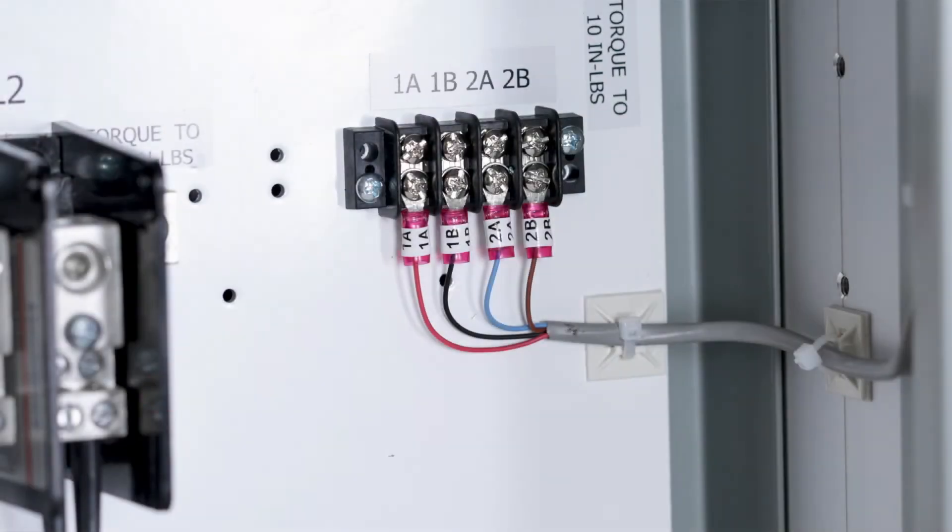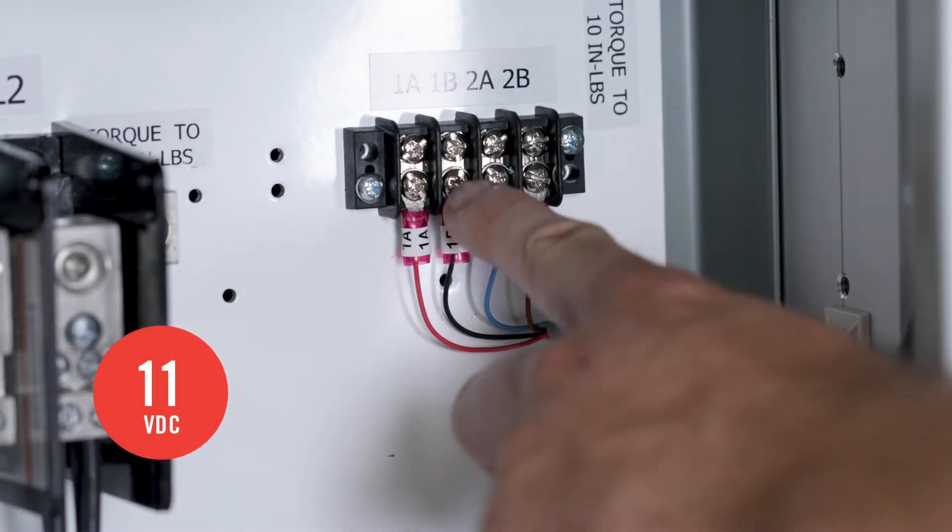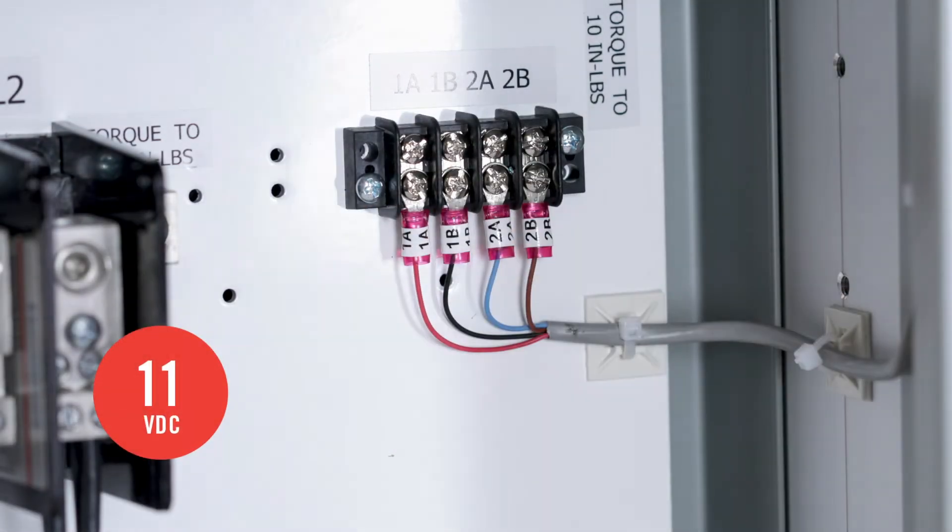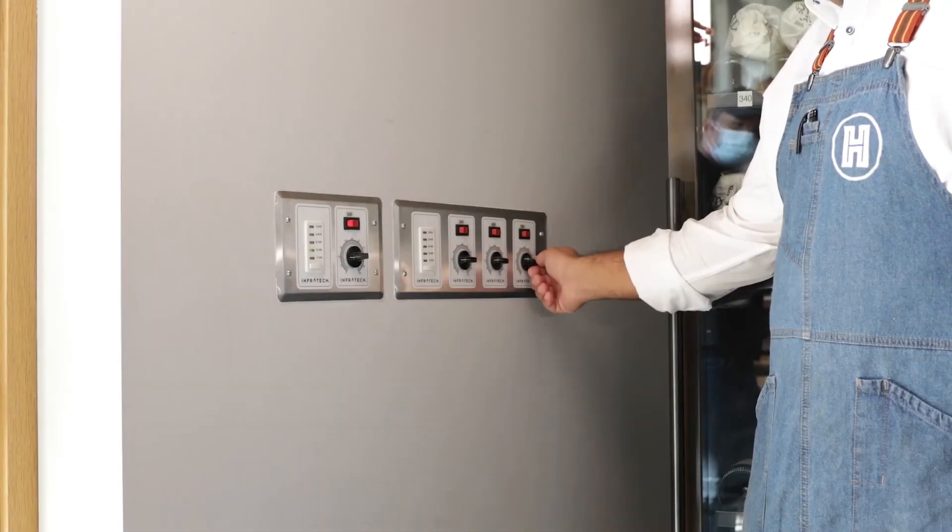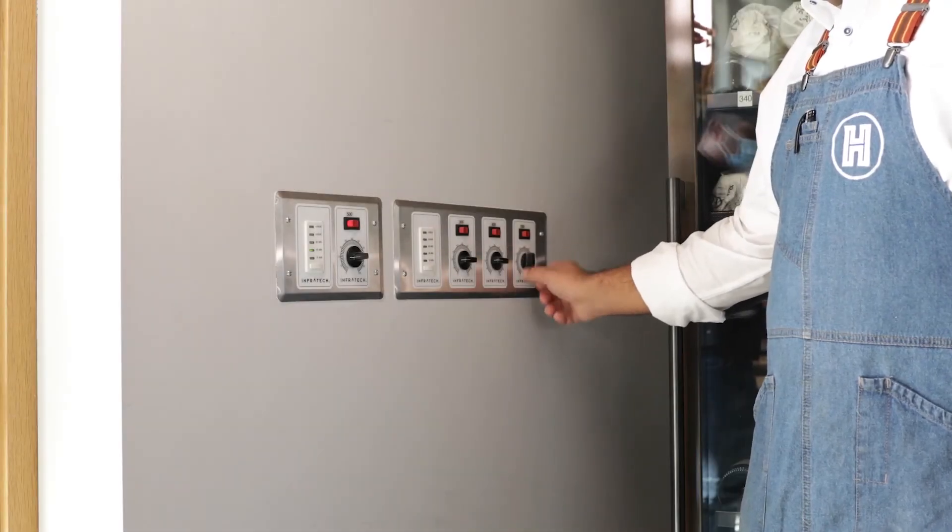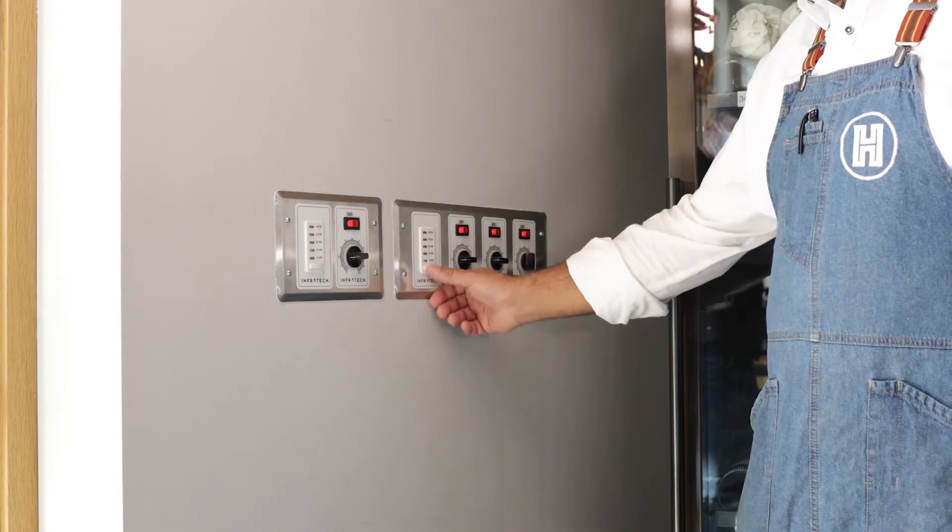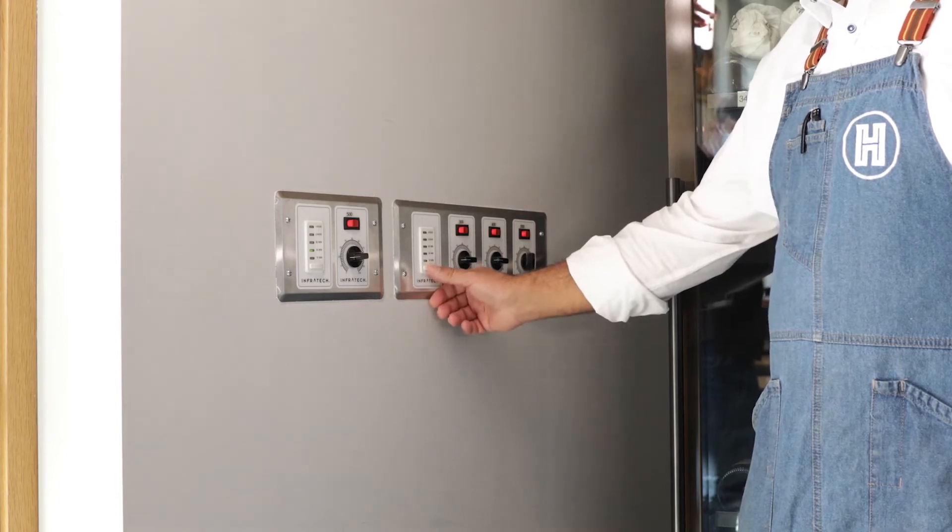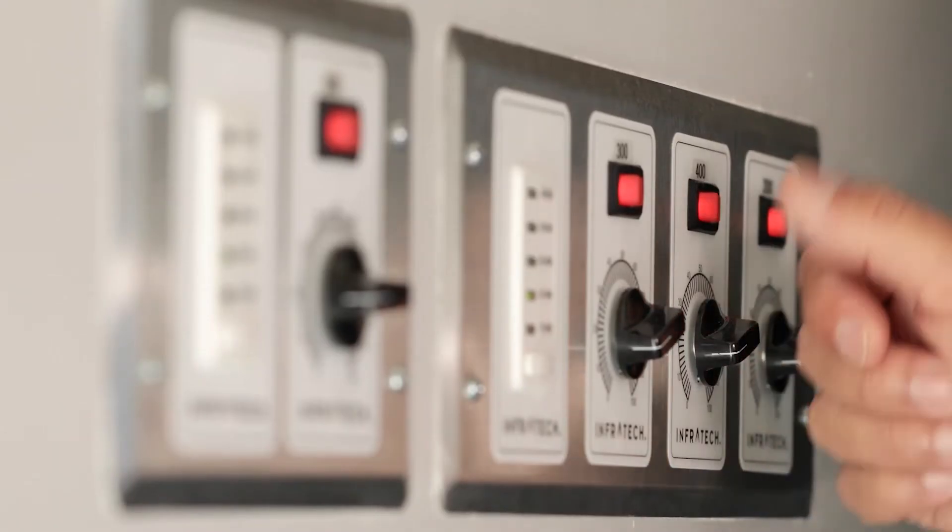Your installation is complete once all of the low voltage signals are connected. To verify a successful installation, check the zone analog controller's output. You should be getting a 0 to 11 volt DC signal.